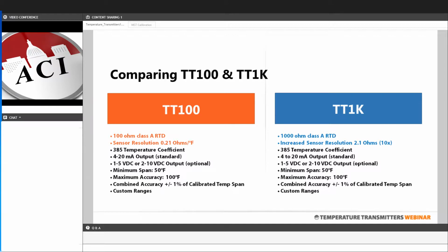4 to 20 milliamps is the standard output for all of our temperature transmitters, with 1 to 5 volt and 2 to 10 volt DC outputs available as options. All of these transmitter boards are calibrated to your specific temperature span that's requested when ordered. There's no standard or default temperature spans. So when you order a temp transmitter from us, you specify what range you want that to be calibrated to, and we set that up linear to the 4 to 20 milliamp output.